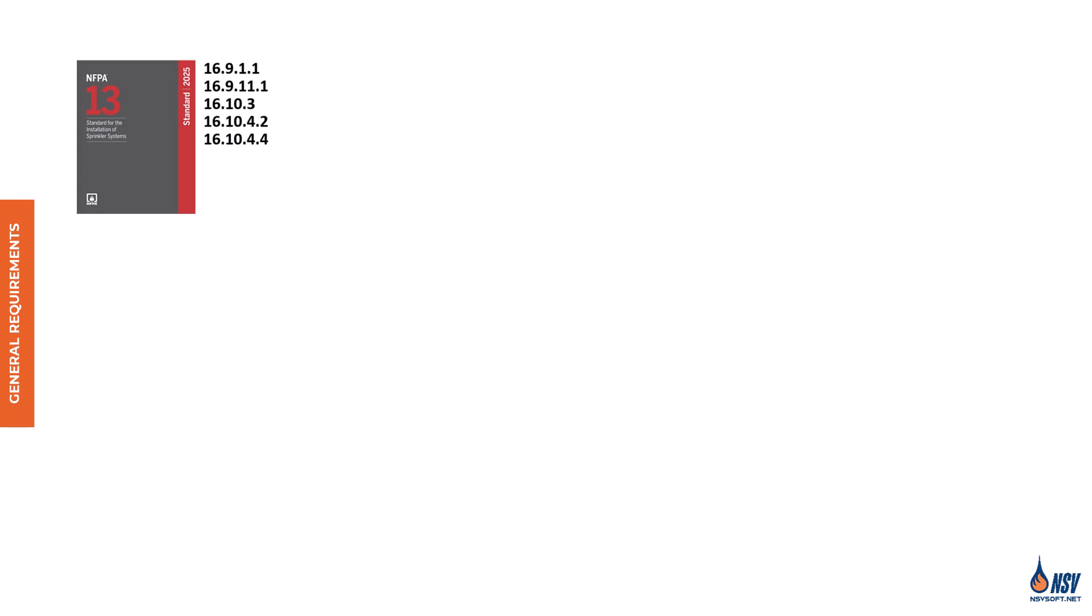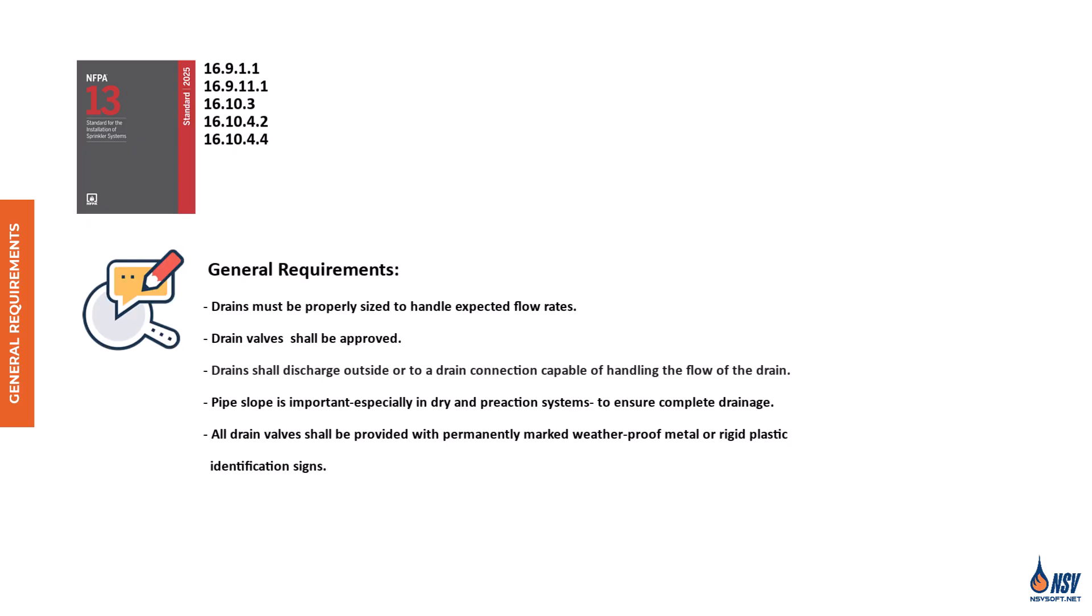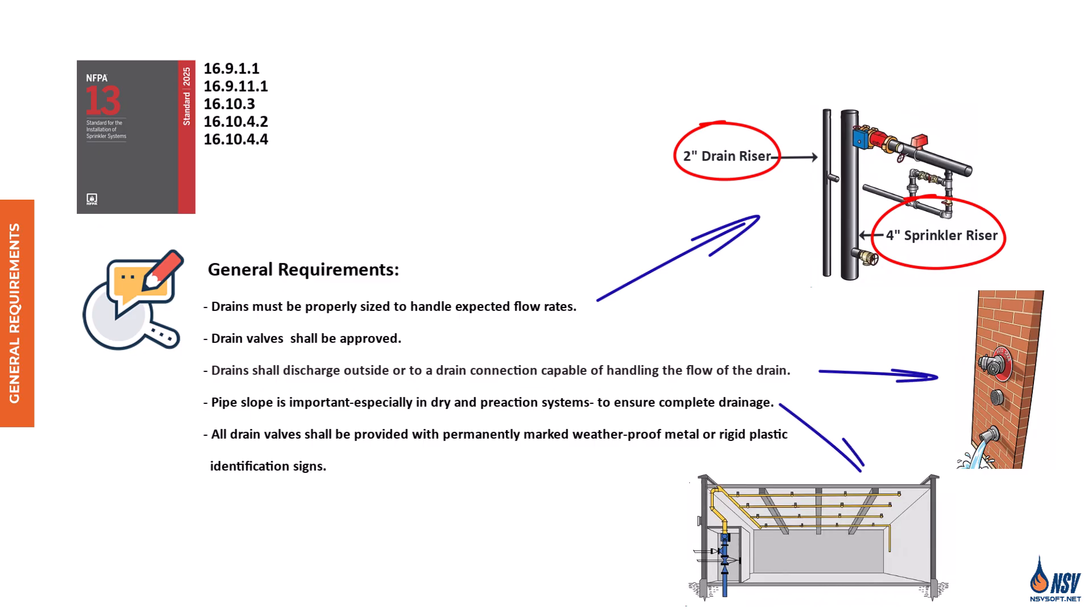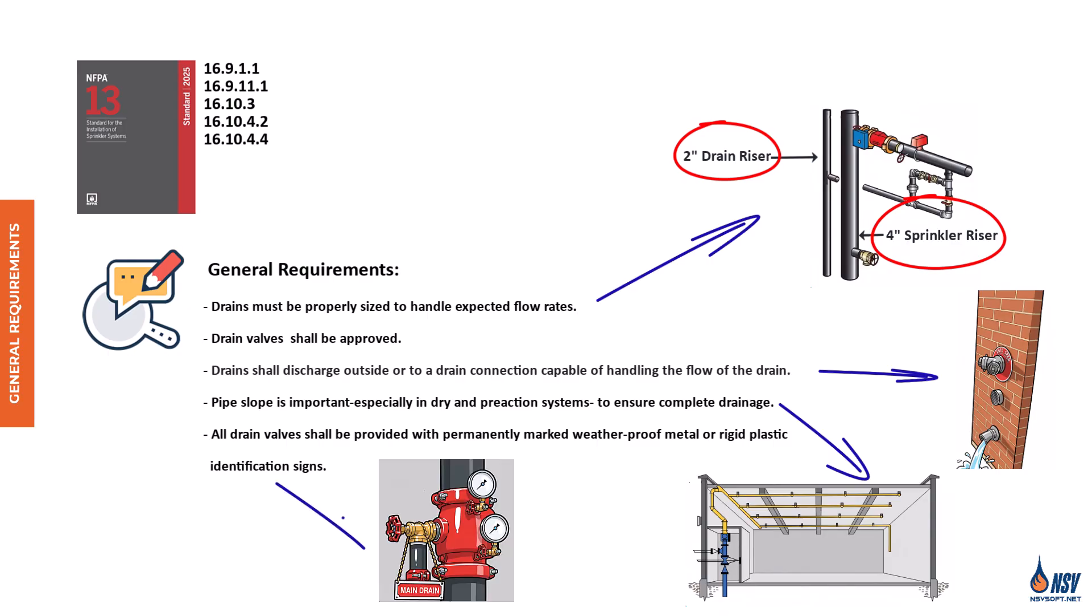According to NFPA 13, 2025 edition, sections 16.9.1.1, 16.9.11.1, 16.10.3, 16.10.4.2, and 16.10.4.4, several general requirements must be met to ensure proper drainage in fire sprinkler systems. Drains must be properly sized to handle expected flow rates. Drain valves shall be approved. Drains shall discharge outside or to a drain connection capable of handling the flow of the drain. Pipe slope is important, especially in dry and pre-action systems, to ensure complete drainage. All drain valves shall be provided with permanently marked weatherproof metal or rigid plastic identification signs. In the following sections, we'll explore each of these requirements in more detail.